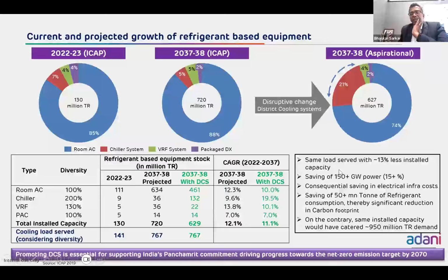What does this mean? This means that the same load is served with 13% less installed capacity, and there will be a saving of about 150 plus gigawatt of power also, if we can make this happen. And this 150 gigawatt of power is going to have a tremendous impact in saving of the electrical infra, including the generation, transmission, distribution, as well as the installation of the substations at every location for serving the air conditioning load. And 50 million ton of refrigerant consumption will be lessened.